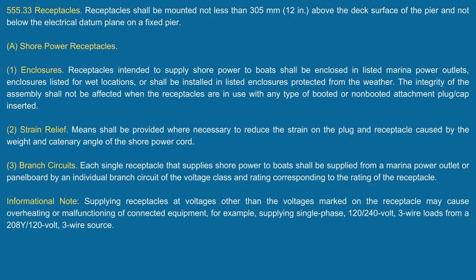Another interesting thing I'll tell all the viewers: the individual branch circuit, if you go look at the definition, says it connects to utilization equipment. So technically you start at the breaker or fuse, the final overcurrent device, and it ends at utilization equipment. Nowhere does it say it ends at an outlet.